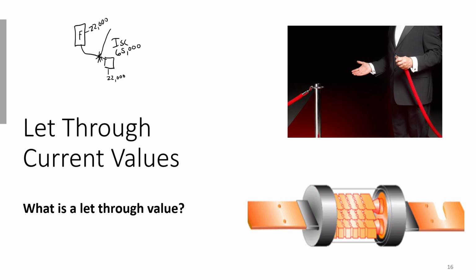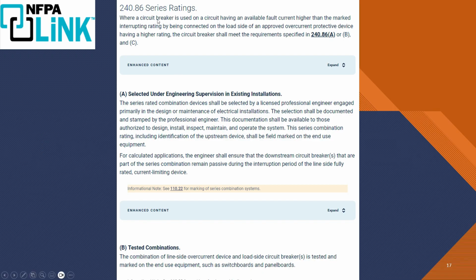I'm not disputing that it works, but the National Electric Code only allows us to do this in existing installations. Here it is. This is a series rating, 240.86 for a series rating. So if I have a device, here are your options. If I have a series rating, I can go with A or B. I'm either allowed to select under engineering supervision in existing installations, I can apply the let-through current of a fuse or a breaker or whatever, or I can use a tested combination system. So if I am using a series rating in a new installation, the only option available to me is B. That's it.